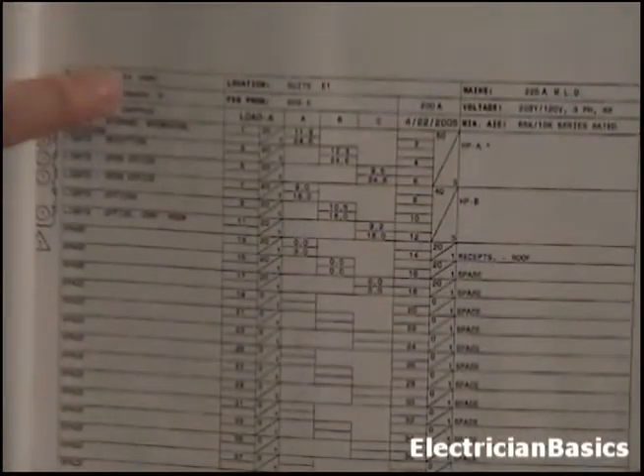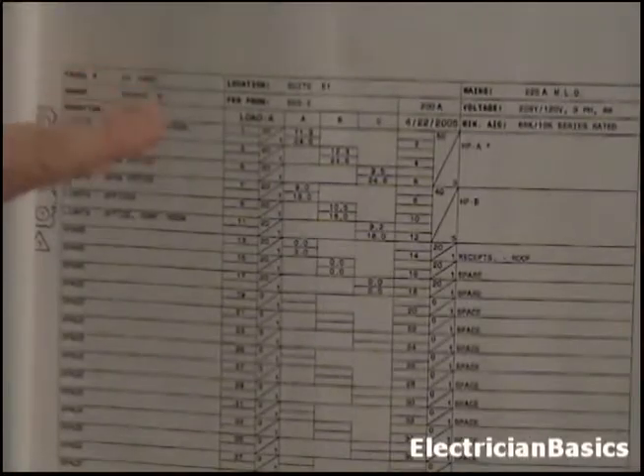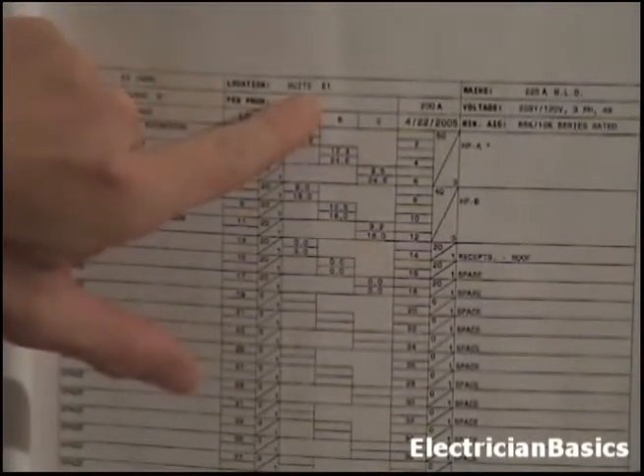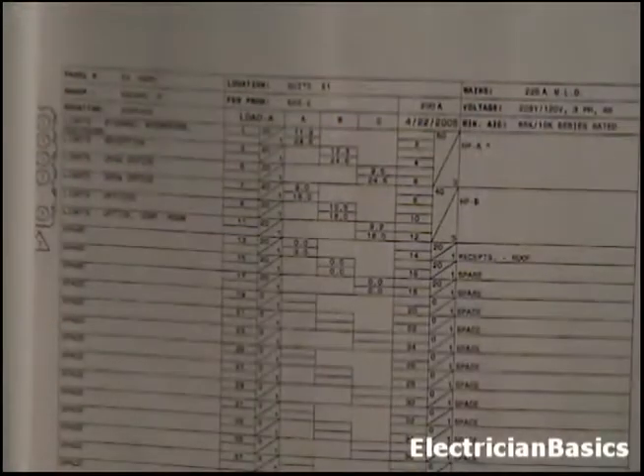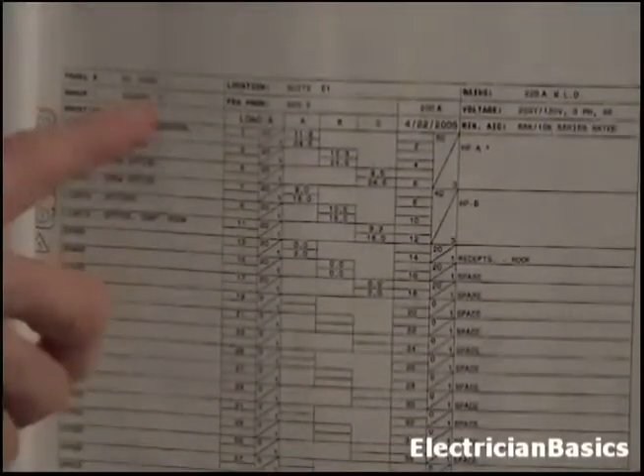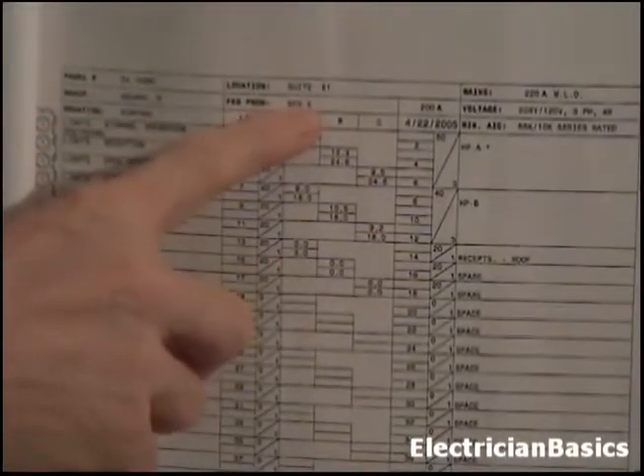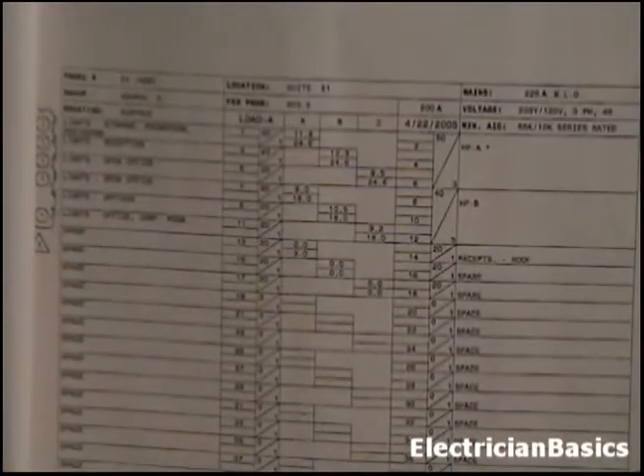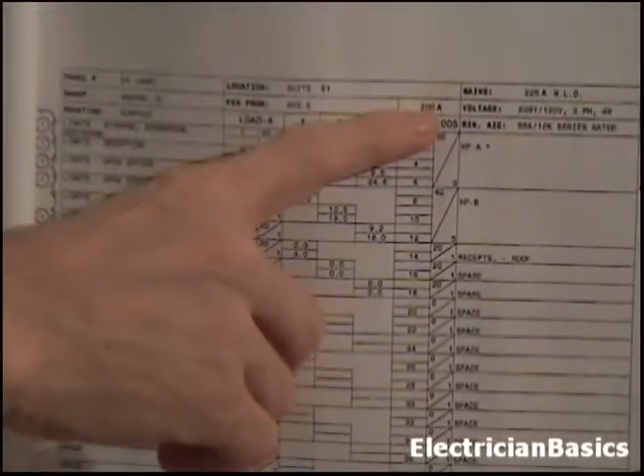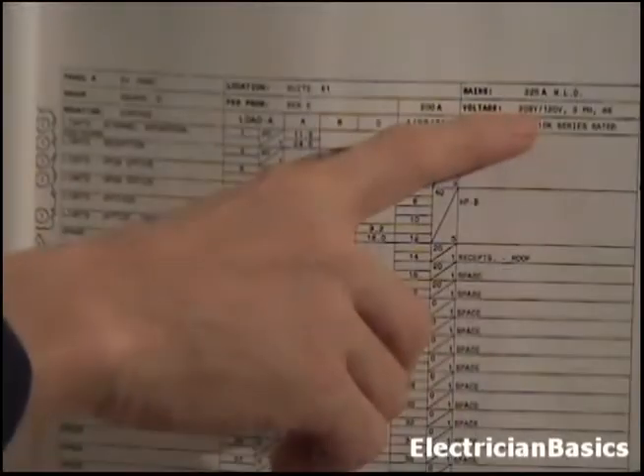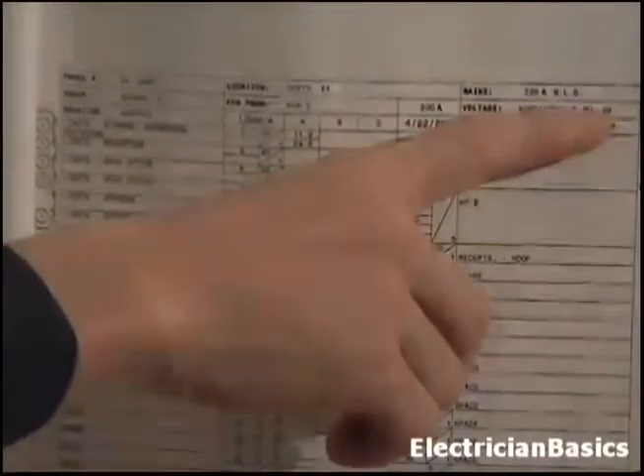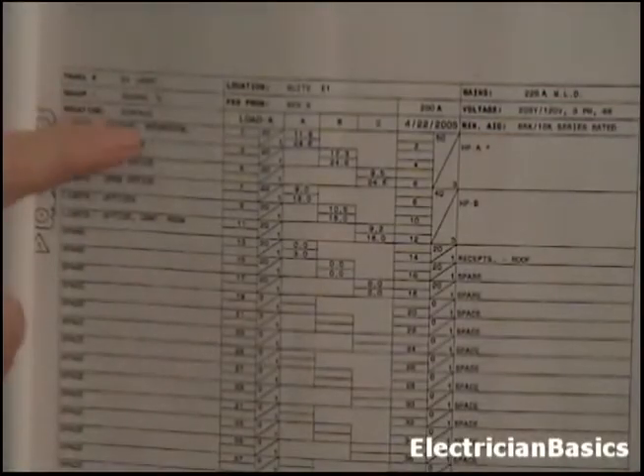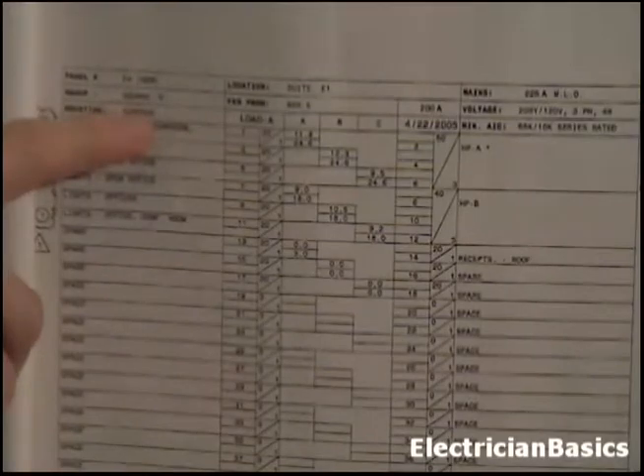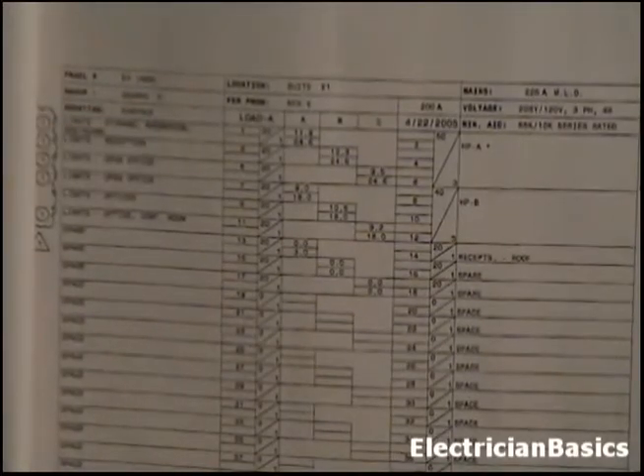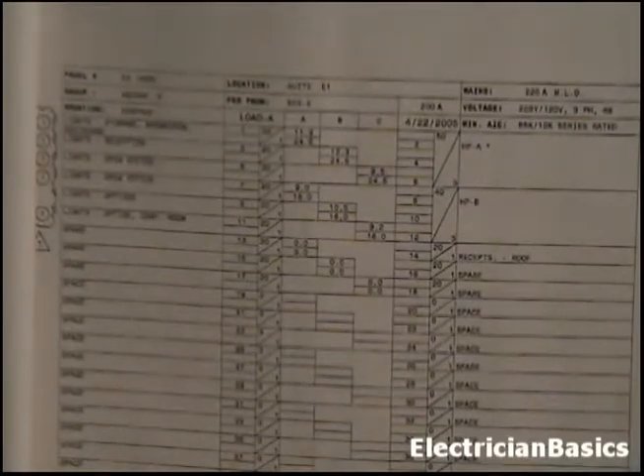So let's look at the top. This is panel E4, and it's a new panel. The location is suite E1, which is where it's built. It says the mains are 225 amps. The manufacturer is Square D. We're fed from the SES, and we looked at that. And of course, from our one-line diagram, we could see that it's going to have a 200 amp breaker there. The voltage is 208 in the Y configuration, 120 volts, 3-phase, 4-wire. Mounting: this panel is surface mounted, which means it's going to be mounted on top of the wall, or the other type would be recessed mounted, where it would be inside of the wall.